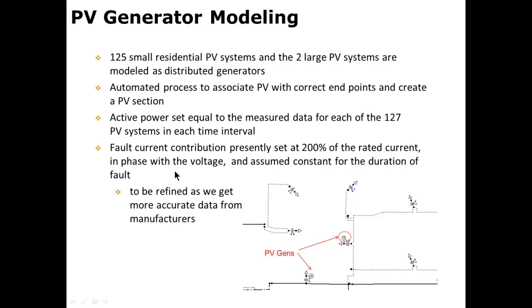What is important for the protection analysis here is the fault current contribution, and that is presently set at 200% of the inverter's rated current, and it is assumed to be in phase with the terminal voltage, and it is assumed to persist at a constant value for the entire duration of the fault. Now, this is the assumption that we're using, and this can be refined as we get more accurate data from the inverter manufacturers.